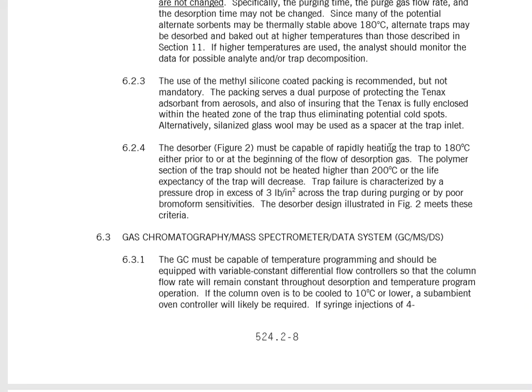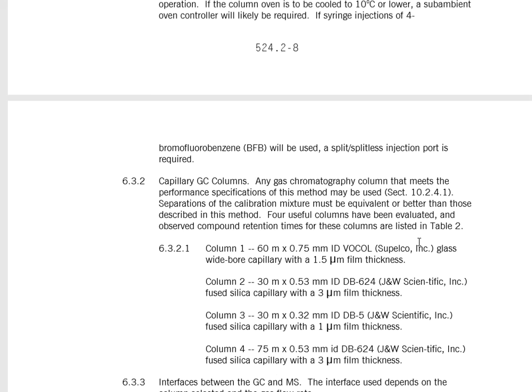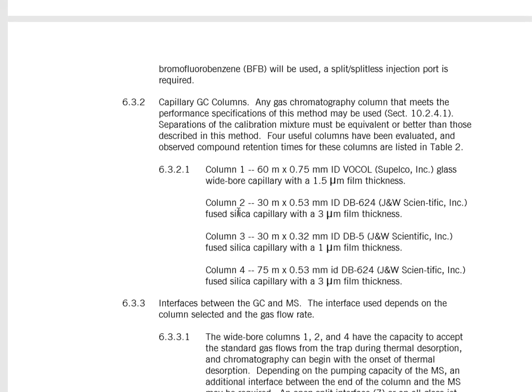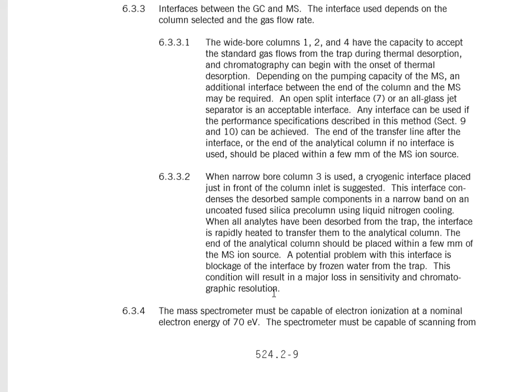The desorber has to be able to heat up to 180°C, and the polymer section of the trap should not be heated higher than 200°C or the trap will degrade. For the GCMS system, there are a couple of column options. They're different lengths — 60 m and 30 m — and different inner diameters: 530 µm, 320 µm, and 750 µm. I just need to make sure I match the method parameters to the proper column.